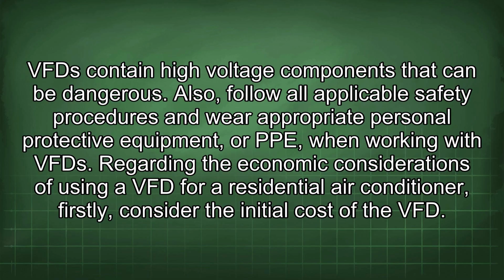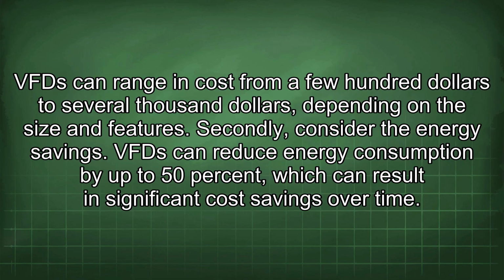Regarding the economic considerations of using a VFD for a residential air conditioner, firstly, consider the initial cost of the VFD. VFDs can range in cost from a few $100s to several $1,000s, depending on the size and features. Secondly, consider the energy savings. VFDs can reduce energy consumption by up to 50%, which can result in significant cost savings over time.